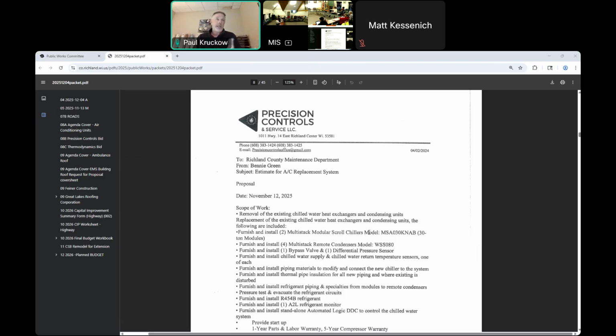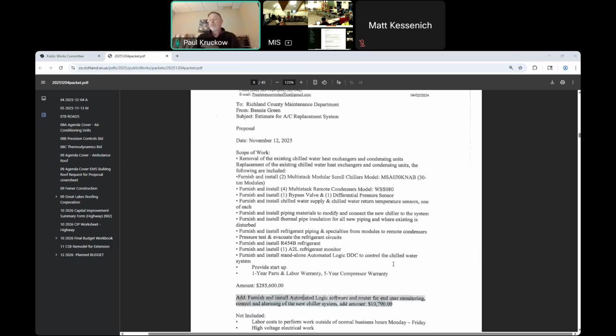We'd have extra usage if we had additional pumps being used. And then there's the loss if there was a heat exchanger, a water to water. We don't have any water to water heat exchanger in this system. It's just the water to refrigerant, whether it's a packaged air cooled chiller or a multi-stack module, you still have your water to refrigerant exchange. So for those reasons, that makes the system more energy efficient to operate, which at the end of the day saves the county some money in energy usage when you're making chill water.